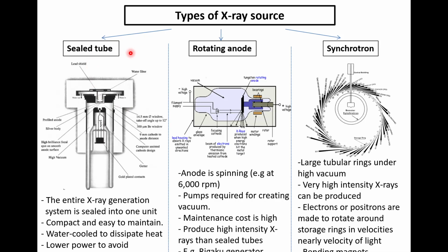Now this is not an everlasting anode, right? It is not made up of diamond or anything that will always stand there and say come electrons, hit me. So it also has a lifetime. If you have something which is fixed and you are continuously hitting it, sometimes you will find that some pores will be produced in that anode, and your anode will be of no use, because now the anode is destroyed.